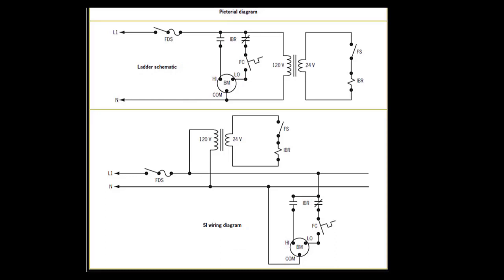When FS is open, the IBR coil is de-energized. At this point, the normally closed contacts remain closed, and the normally open contacts remain open. When FC is closed, the BM runs on low speed.